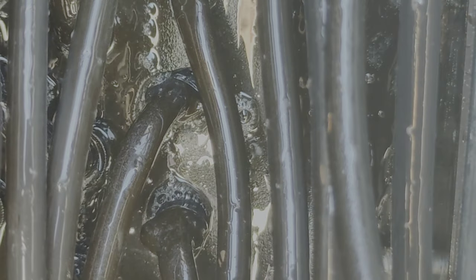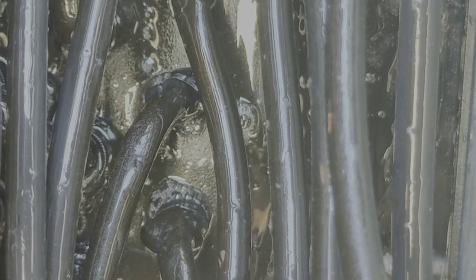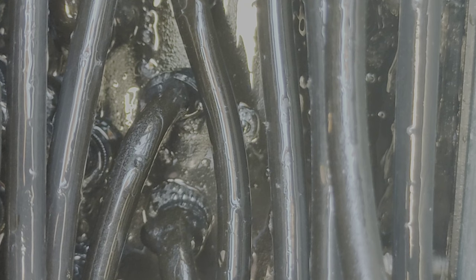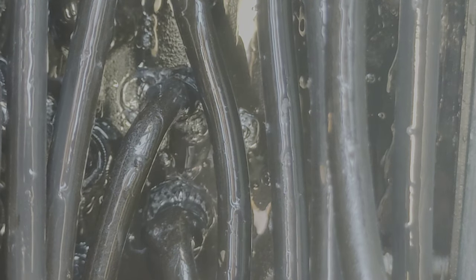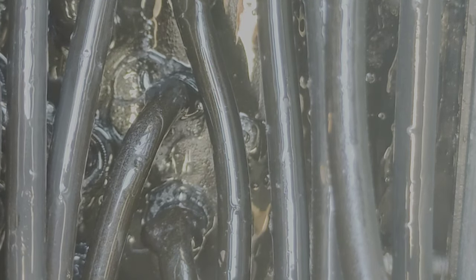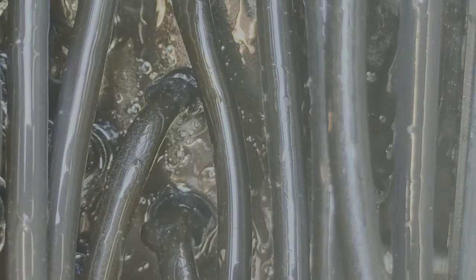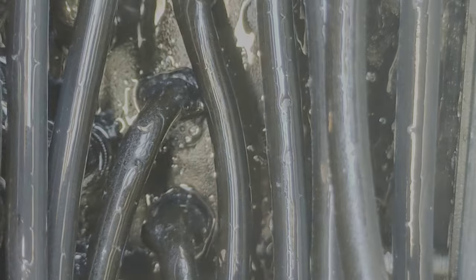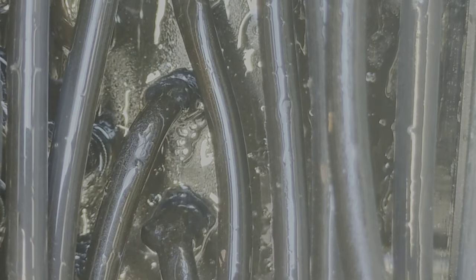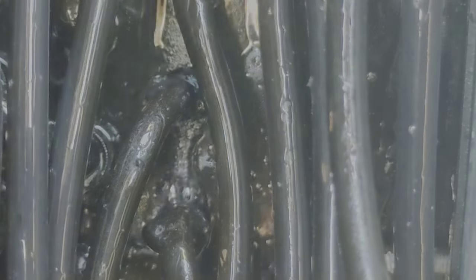Alright, so finally I have pinpointed it. It is going to be right there, that tube coming from the left hand side. Oh, there you see it right there, no denying that. And that's just like 50 or 60 psi of standing pressure. Can you imagine how severe that leak was when it was full of liquid?